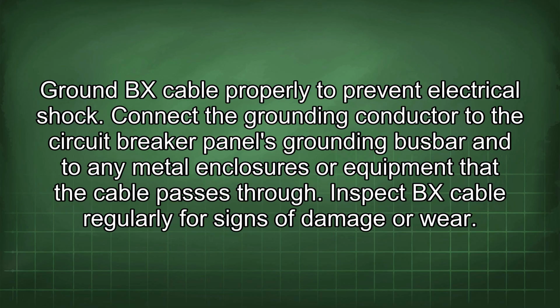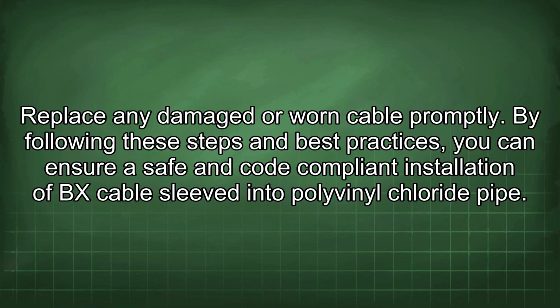Ground BX cable properly to prevent electrical shock. Connect the grounding conductor to the circuit breaker panel's grounding busbar and to any metal enclosures or equipment that the cable passes through. Inspect BX cable regularly for signs of damage or wear. Replace any damaged or worn cable promptly.